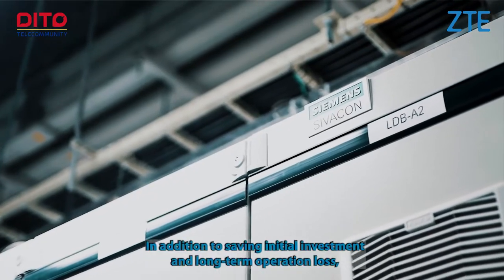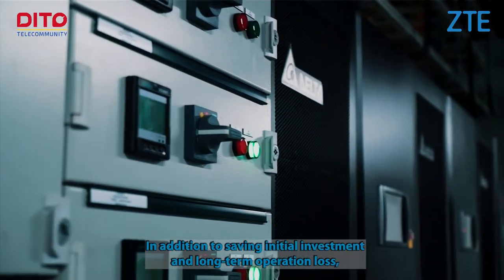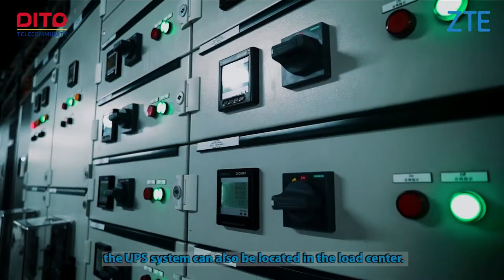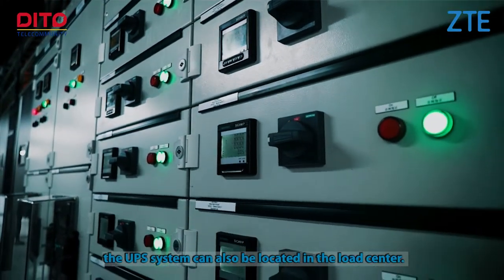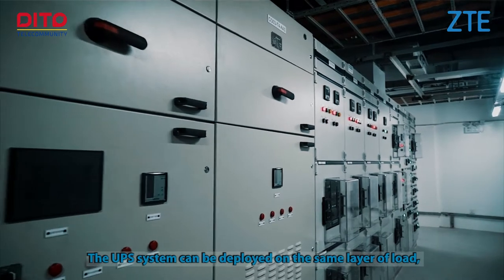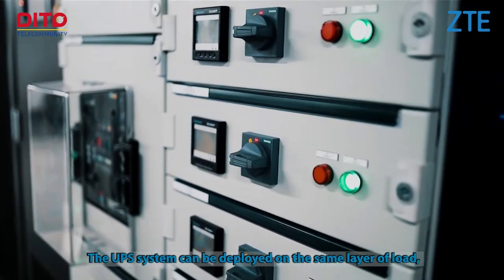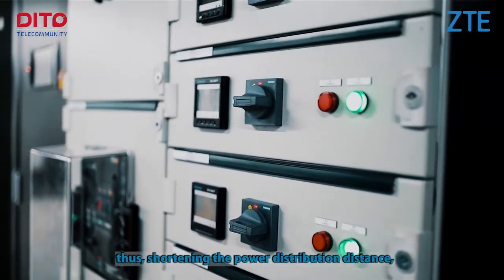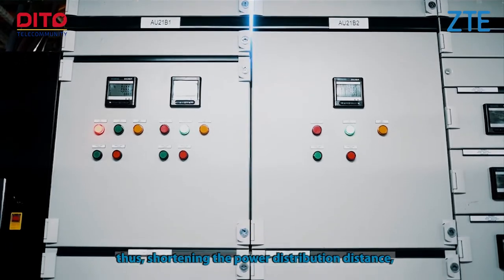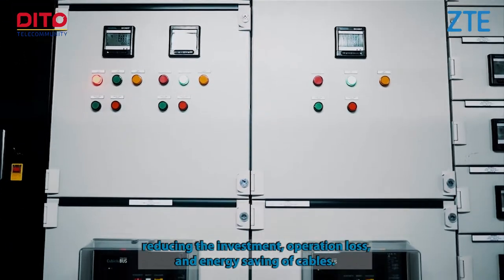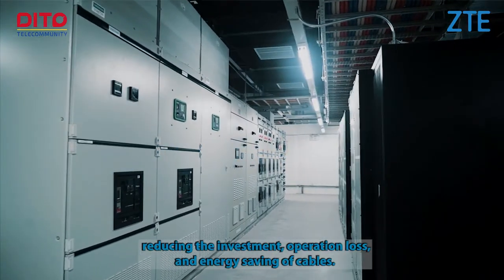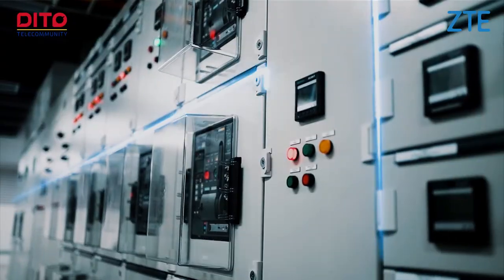In addition to saving initial investment and long-term operation loss, the UPS system can also be located in the load center. The UPS system can be deployed on the same layer of load, thus shortening the power distribution distance, reducing the investment, operation loss, and energy saving of cables.